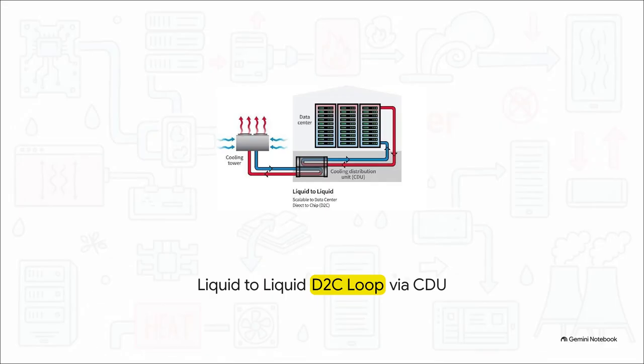Once that liquid absorbs the heat from the chip, where does it go? If you follow the flow, the hot liquid cycles out of the server rack and flows into what's called a cooling distribution unit, or CDU. Inside the CDU, the heat is transferred through a liquid-to-liquid heat exchanger. The now cooled primary liquid is pumped right back to the chips to do it all over again. Meanwhile, the secondary liquid loop takes that transferred heat entirely outside the building, often to a cooling tower.